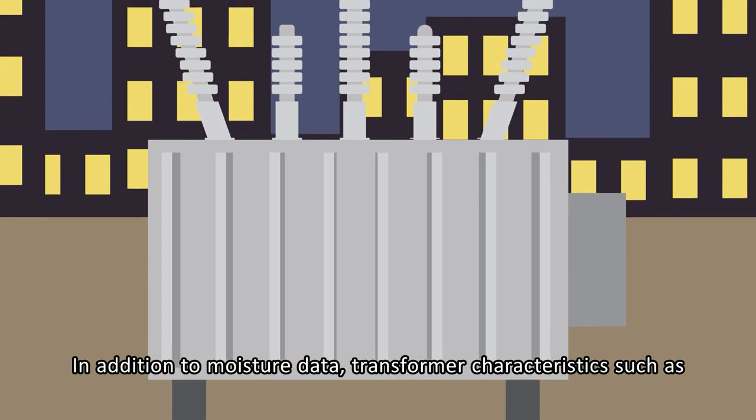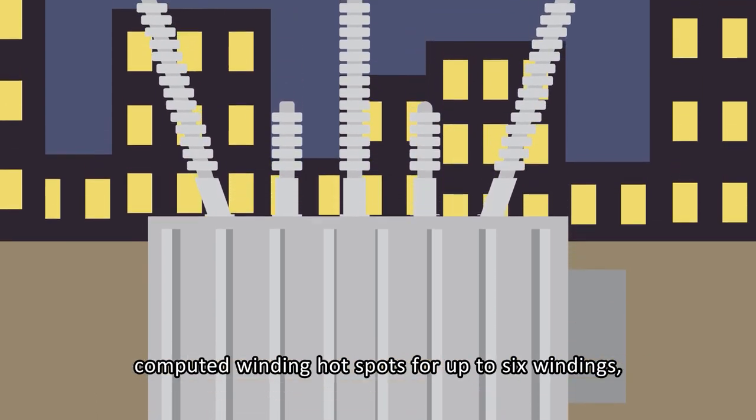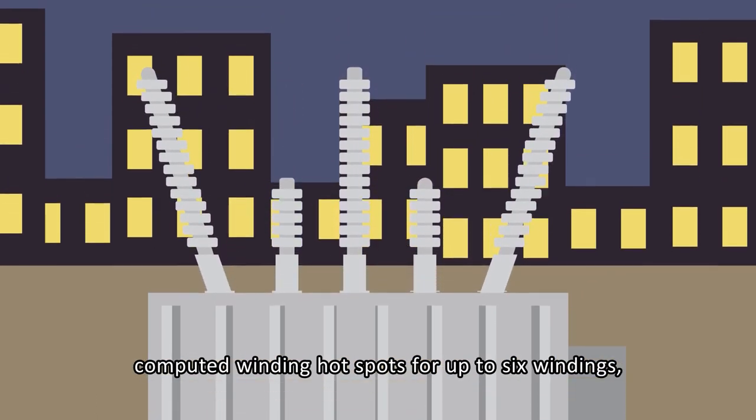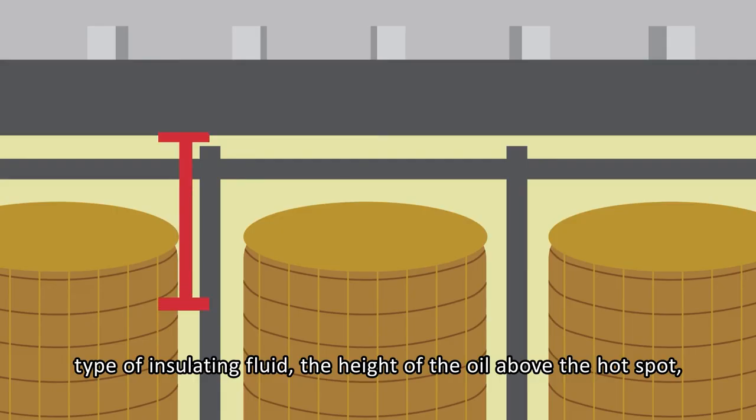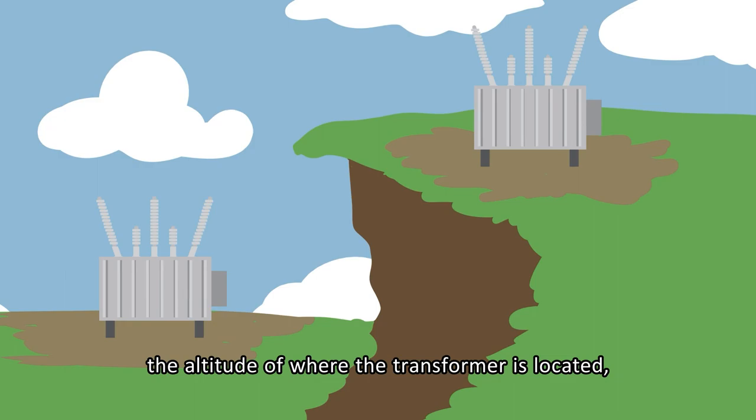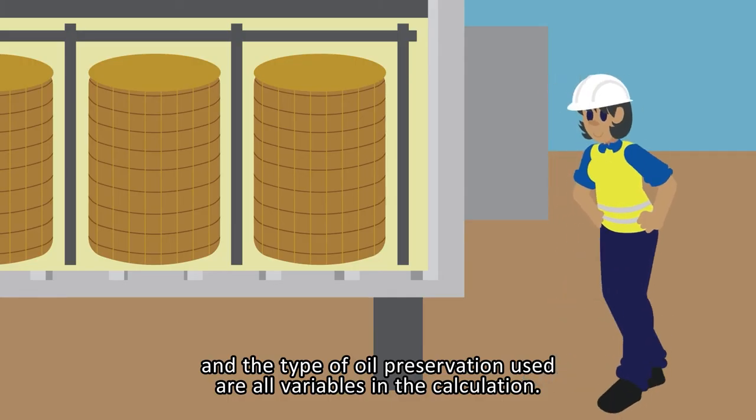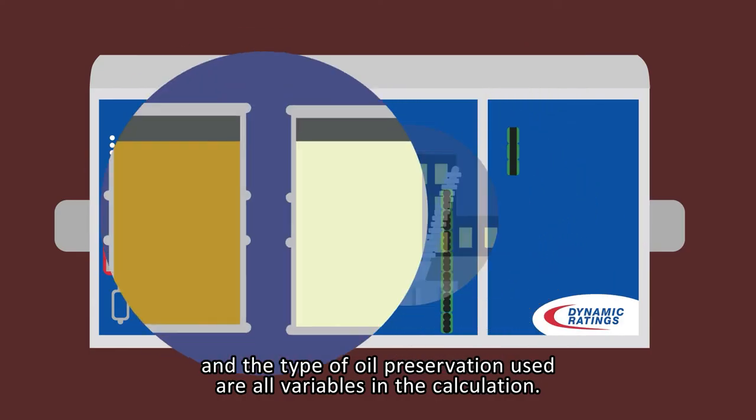In addition to moisture data, transformer characteristics such as computed winding hotspots for up to six windings, type of insulating fluid, the height of the oil above the hotspot, the altitude of where the transformer is located, and the type of oil preservation used are all variables in the calculation.